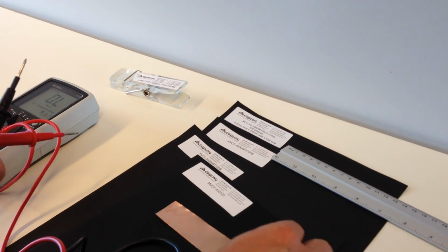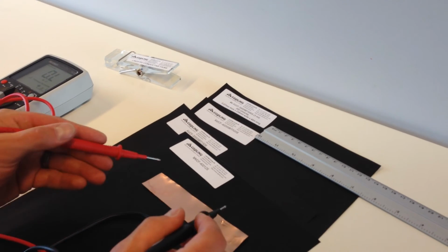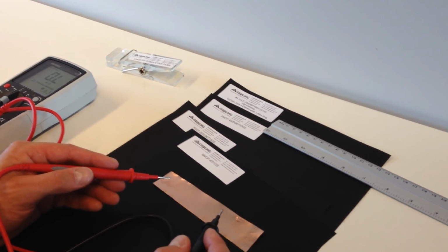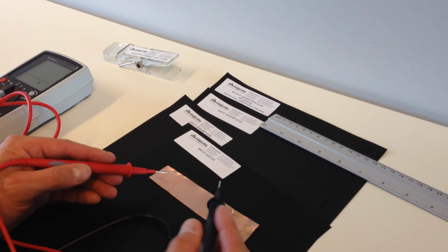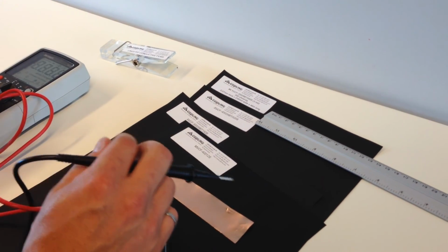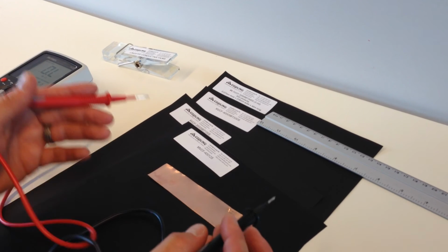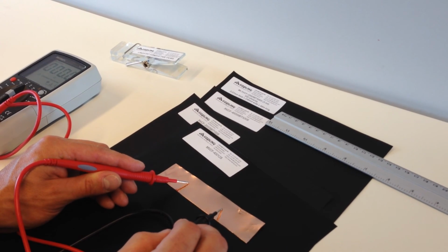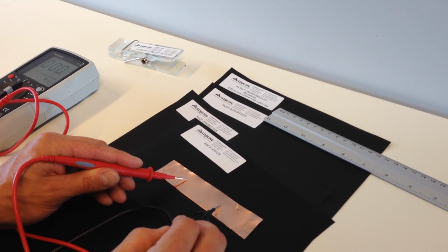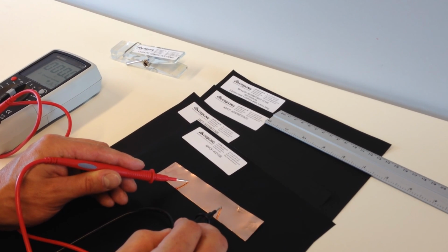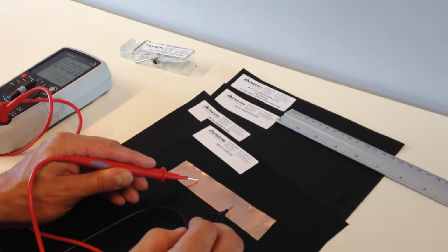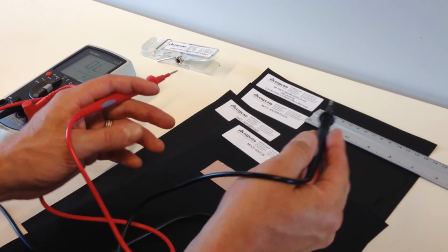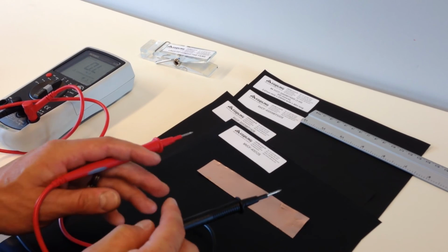Just to give you an example of how that compares to a conductive material, if you take this thin strip of copper foil, also a product that we sell under the Linqstat name, copper, as you would expect, is a conductor, so the value that you would expect in ohms for resistance is 0. And if you look at the multimeter, you can see indeed that the value that you get for the copper strip is 0 ohms per square, so all the values of all these conductive films are relative to a value of 0.